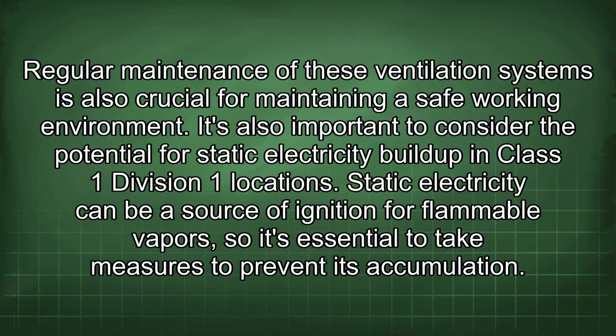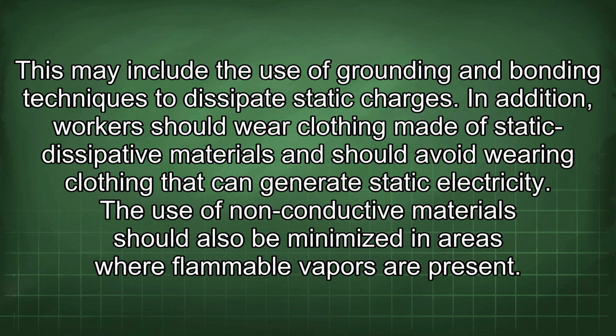It's also important to consider the potential for static electricity buildup in Class 1 Division 1 locations. Static electricity can be a source of ignition for flammable vapors, so it's essential to take measures to prevent its accumulation. This may include the use of grounding and bonding techniques to dissipate static charges. In addition, workers should wear clothing made of static dissipative materials and should avoid wearing clothing that can generate static electricity. The use of non-conductive materials should also be minimized in areas where flammable vapors are present.